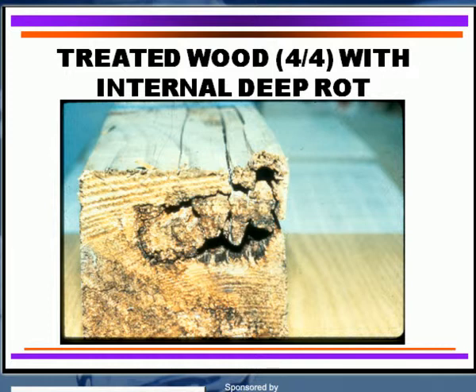What you need to do is go around to your cooling tower and determine if you do have wooden structures there, is there any internal decay. Do not use an ice pick or a sharp instrument to probe that wood surface. That would just open up new spots that would penetrate the preservative layer and allow the decay organism to enter. What you need to use is a blunt instrument to see if there's any softness to it.